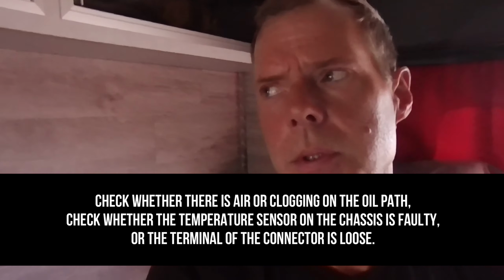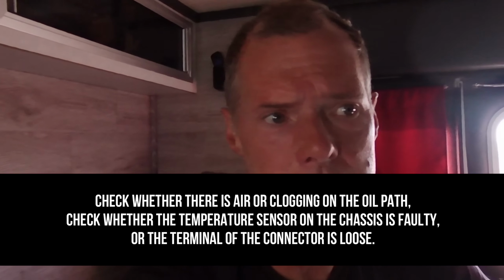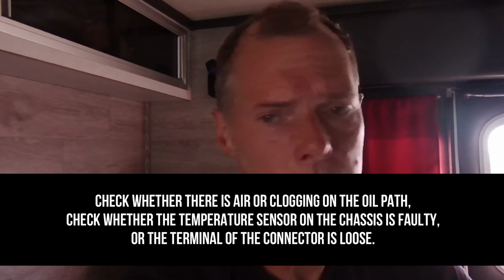And it gave me an error code, E08. So when you look at the English troubleshooting sheet, E08 talks about blockage in the fuel line, mainly blockage in the fuel line. It also talks about making sure that the temperature sensor connections are good. Well, this model doesn't have a temperature sensor, a chassis temperature sensor. It doesn't have that. It started, it ran, it shut itself off.